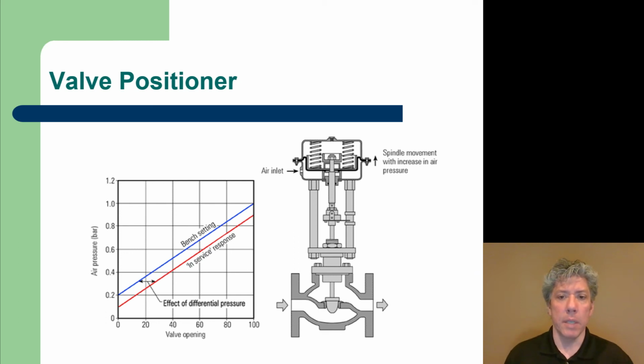Now, another problem is that there's a difference between the setting when you've got the valve out of the process and when it's in the process and fluid is actually flowing through it. If you think about the fluid flow going through the valve, there's a significant restriction around the plug, right? And so the fluid is going to apply a force to the plug, and so the amount of pressure required to get a particular valve position will be different than if the fluid is not flowing. And so there's something called a bench setting, where essentially the valve is not in the process and you apply pressure to the diaphragm in order to get varying positions of the valve body. The response of valve opening versus air pressure is different than when you have the valve in the process and fluid is flowing through the valve. And so in service, the response of the valve will be a little bit different.